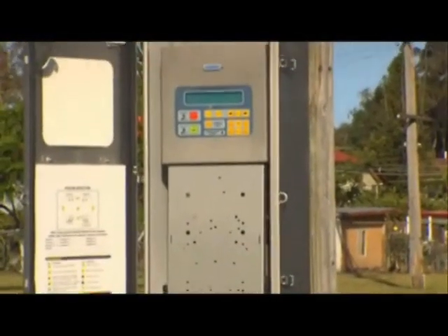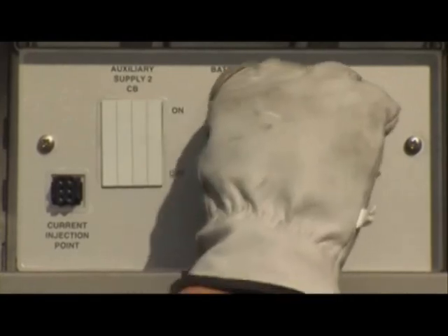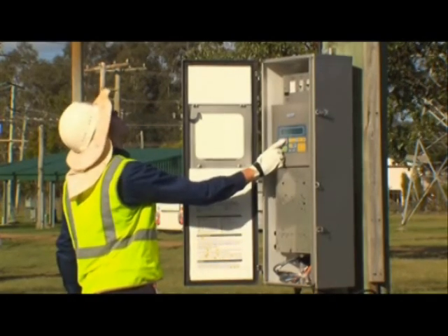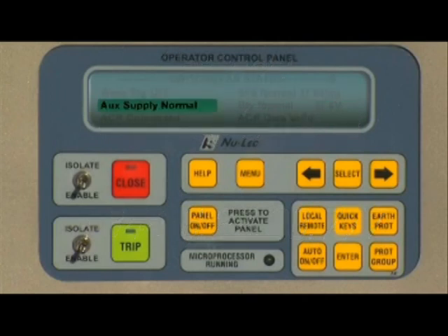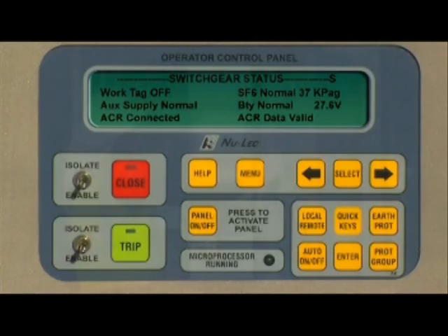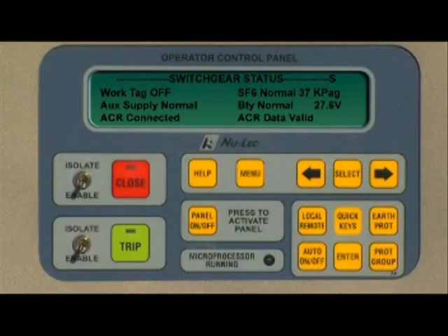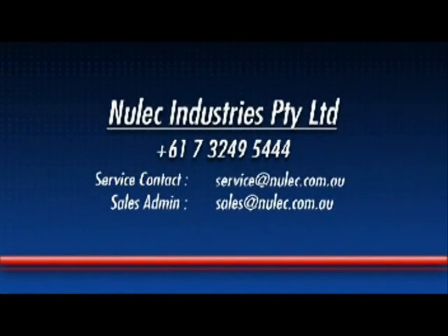Once the control cable and earth connections have been completed, the controller can be powered up by switching on both MCBs. A quick diagnostic test can be completed by cycling to the switchgear status screen on the front panel. For normal operation, this screen should read: SF6 pressure 37 kilopascals, auxiliary supply normal, battery voltage 27 volts, ACR connected, ACR data valid. If all these status points are satisfied, the switchgear can be successfully operated. If there are complications with your installation, please refer to the N-Series technical manual, or for any further questions on the N-Series automatic circuit recloser or any other Nulec products, please contact Nulec Industries directly.